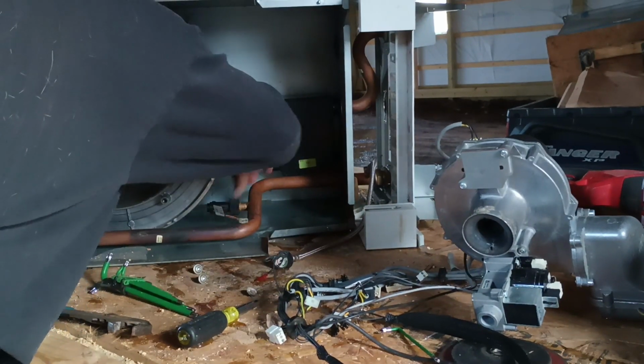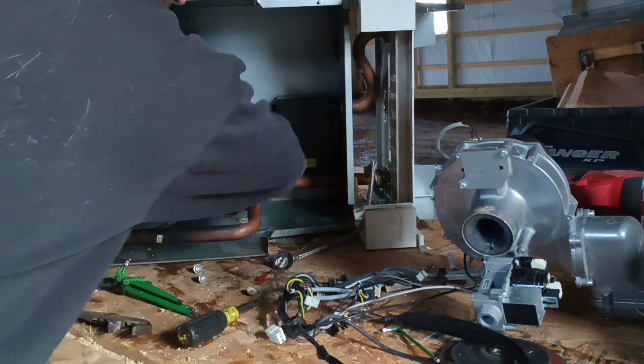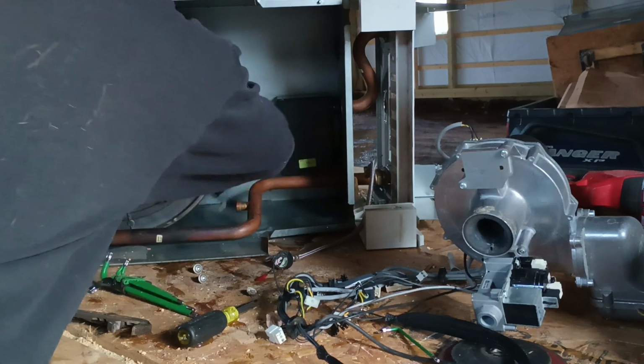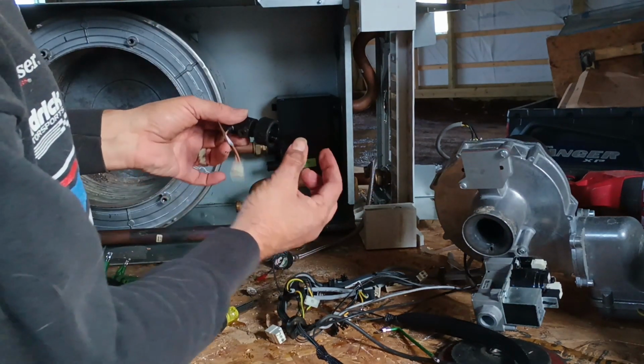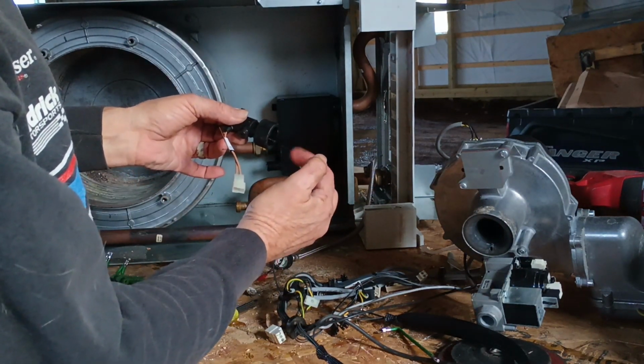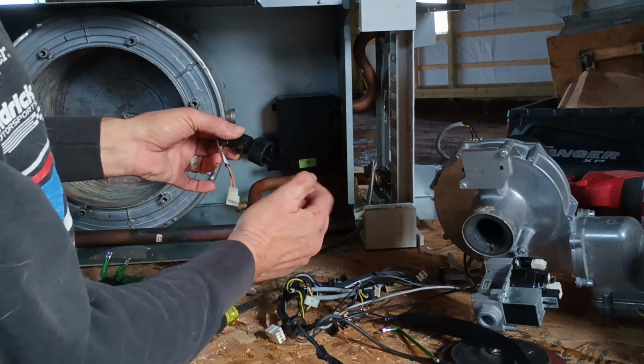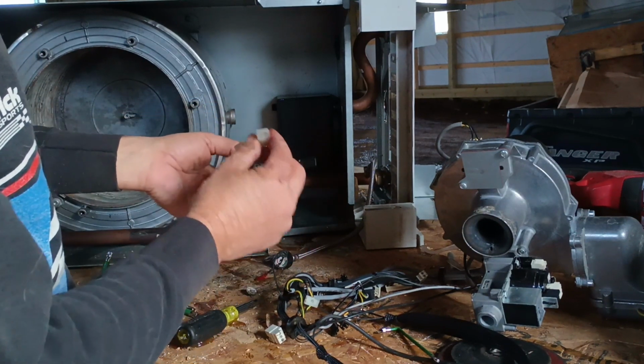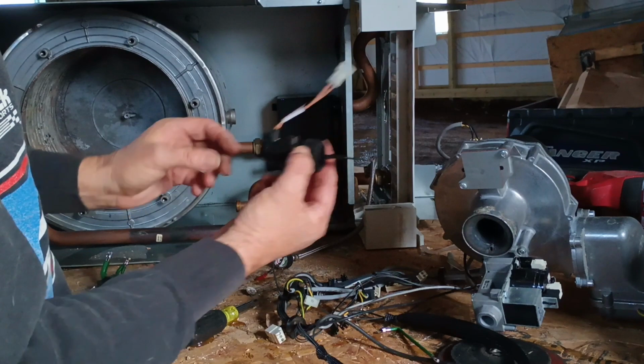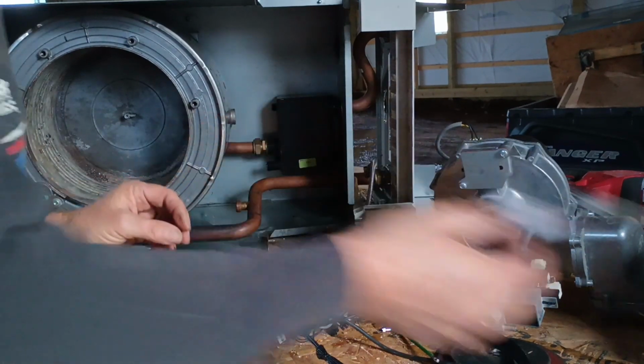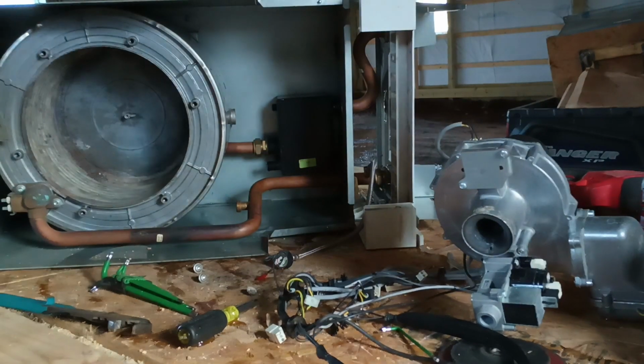This part is the flow switch. So there's a little paddle in here. As the water is flowing through the boiler, this paddle will flip, close the contacts, and prove the safeties that you actually have flow before you fire the boiler. Pretty important.